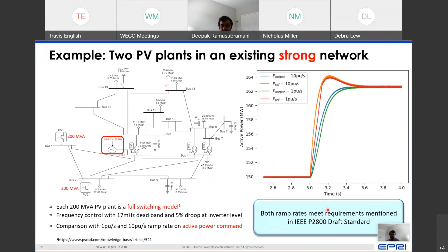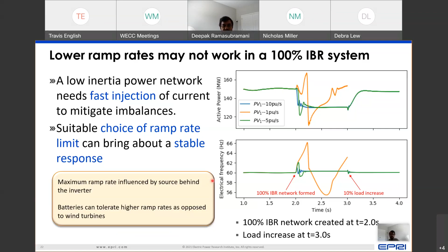And the maximum ramp rate that you see from these inverter-based resources is influenced by the characteristics of the energy source behind the inverter-based resource, which means that as you are getting new resources into the system to provide frequency response, you have to be cognizant of whether that's a wind resource, a solar resource, or a battery resource, because it can play a role in how you get frequency response from these resources in the time frame of interest. If you can do only 2 per unit per second versus 5 per unit per second, with a lower ramp rate limit, you might need more resources to provide the frequency response that you want. Whereas if you have a higher ramp rate limit, which means a faster acting resource, you can need a lesser number of resources to provide this response.